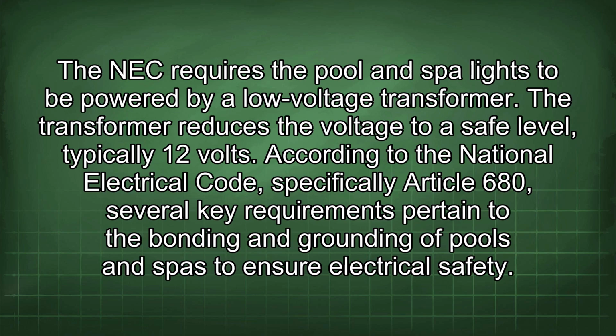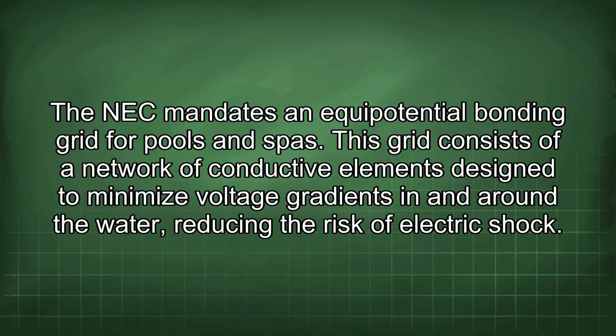According to the National Electrical Code, specifically Article 680, several key requirements pertain to the bonding and grounding of pools and spas to ensure electrical safety. The NEC mandates an equipotential bonding grid for pools and spas. This grid consists of a network of conductive elements designed to minimize voltage gradients in and around the water, reducing the risk of electric shock.